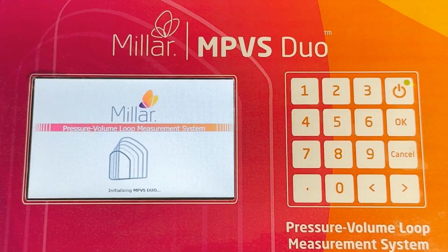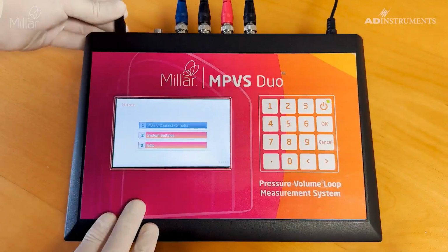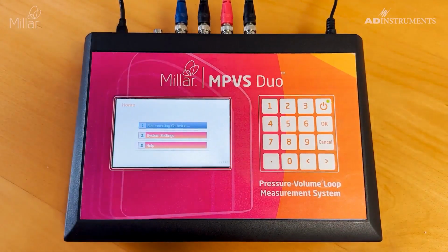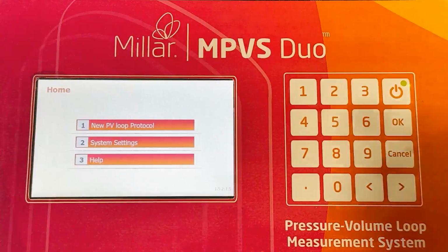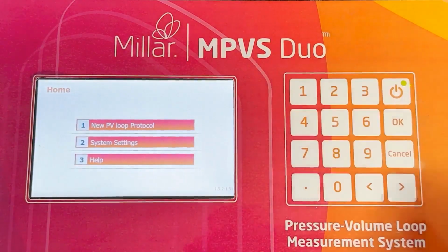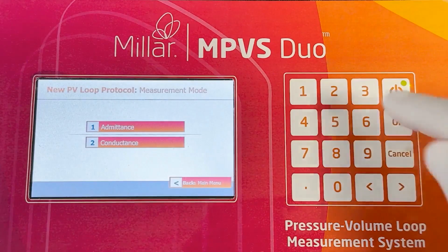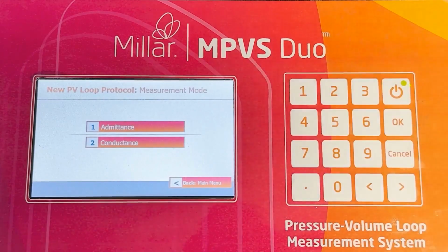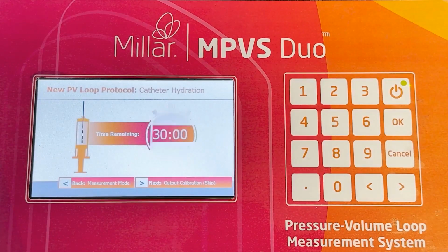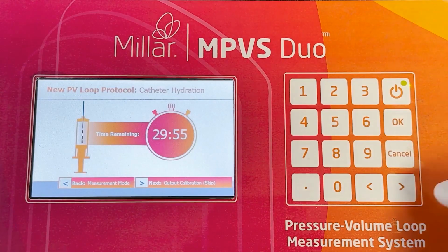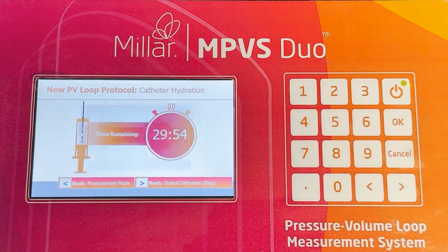Once the MPVS Duo has initialized and with the catheter connected, press 1 to start a new PV loop protocol, and then again on 1 to select admittance. You will now be prompted to soak the catheter for 30 minutes. If the catheter has already been soaking for 30 minutes, you can press the forward arrow to go to the calibration screen.